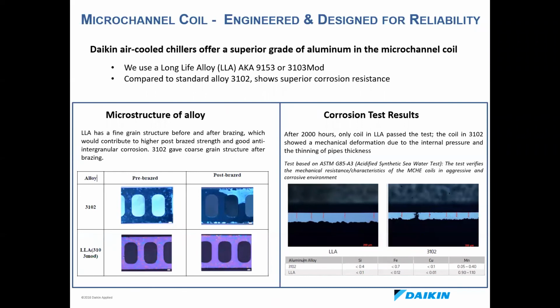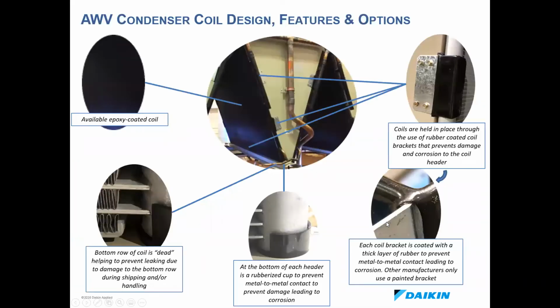We'll skip that. That's just a test showing our aluminum alloy versus the standard aluminum alloy. Over 2,000 hours of a spray test, ours didn't see any breaking. Here's just a little more on the microchannels, a closer look at the epoxy coils. All of the bottom rows of our coils are going to be dead so that when you're shipping or handling the coils, it lessens the chance of a catastrophic burst or leak. At the bottom of each header, you're going to have rubberized cups to help with vibration and also damage and corrosion. And anywhere there's metal-to-metal contact where it's connected to the metal frame of the unit, it'll also have a rubber gasket.